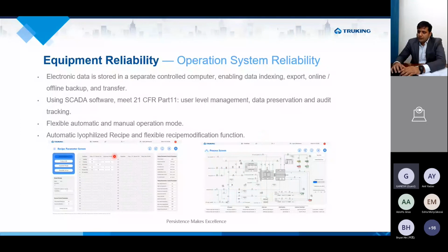For example, this is the documentation; with all the mimics and everything, you can have an audit trail. Then there is a complete P&ID mimic that the operator can use in the SCADA software to see which valve is open, which compressor is working, which vacuum pump is working, at what stage, what the temperature of the chamber is, and what the temperature of the condenser is. All these parameters can be seen in a very interactive way, which also ensures the equipment is reliable enough for better process control. That is very critical.